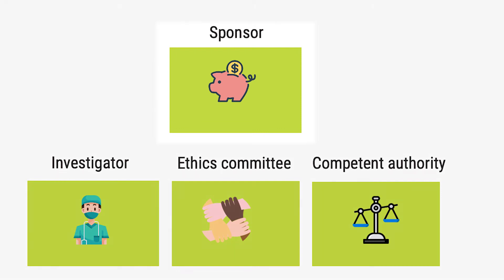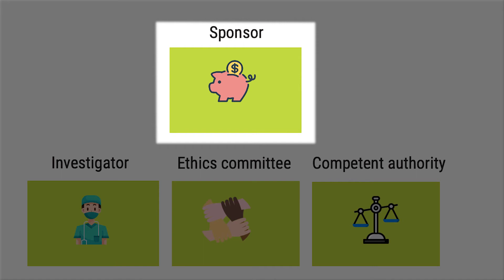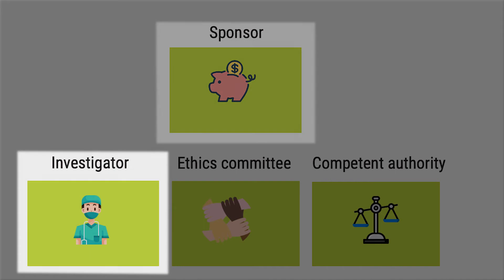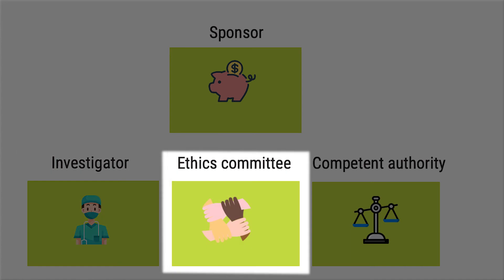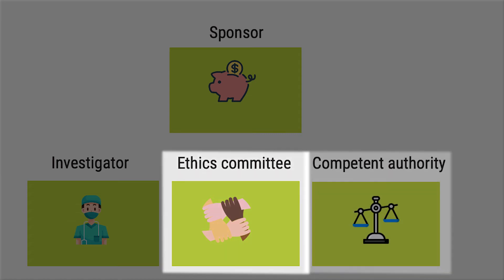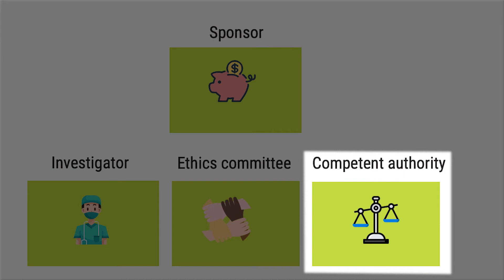The sponsor is ultimately responsible for the clinical investigation — its quality, planning, conduct, and ensuring appropriate communication with regulatory authorities such as the competent authority. The investigator is responsible for the day-to-day conduct of the clinical investigation and must be qualified by education, training, and experience. The ethics committee is the independent body that gives opinions on ethical and scientific matters, and the competent authority is the regulatory body that acts on behalf of the government to ensure legal requirements are applied. Any stakeholder can, often unknowingly, breach the requirements outlined in GCP and the ISO 14155 standard.